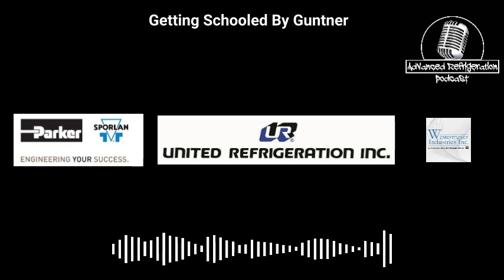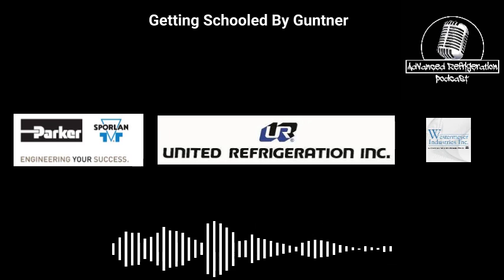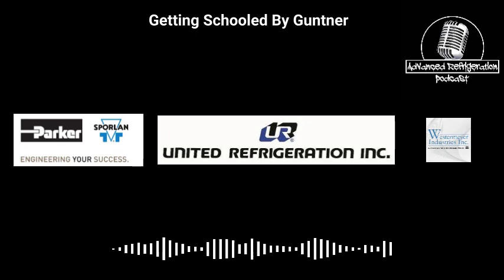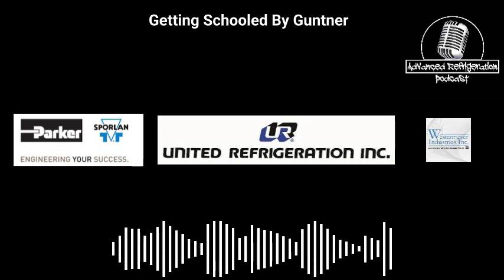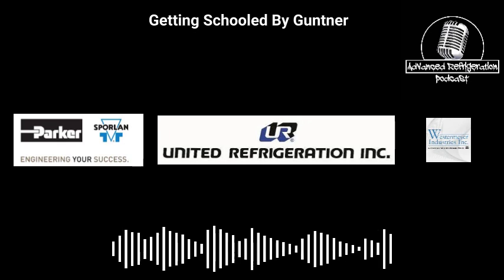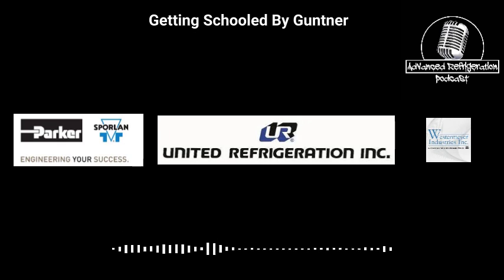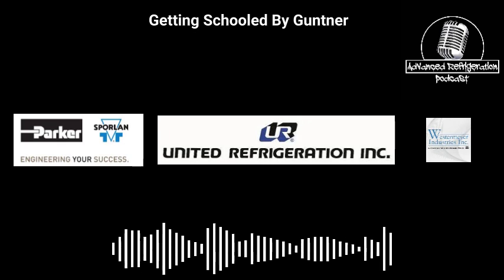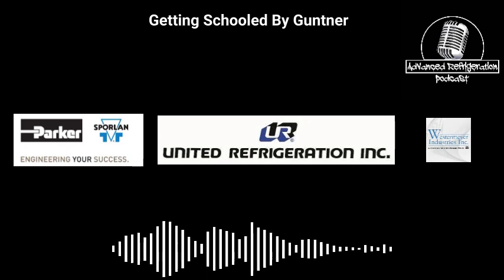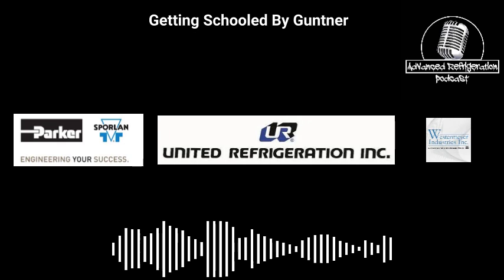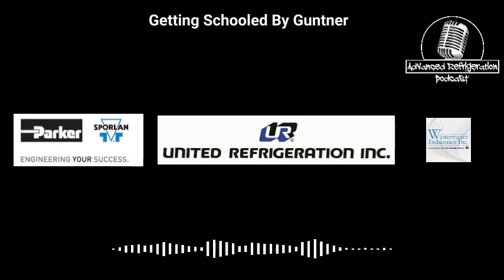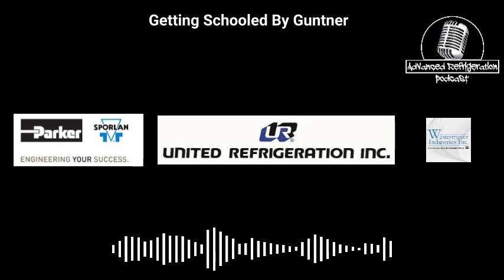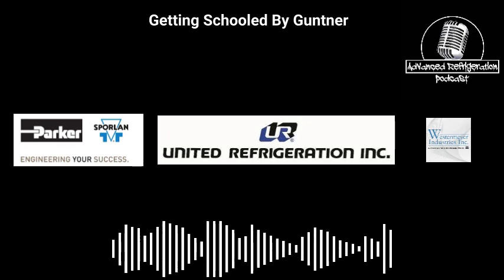There are also a lot of different settings on here. On the controller, you can do a secondary set point. This is usually used on a unit that's standalone. A lot of sites have standalone units and don't have a BMS system. A lot of grocery stores have it standalone, but they might need two set points, one for winter and one for summer. If you have it set up properly with the proper sensors, you can put two set points in the controller, and based on the ambient temperature, our controller will know when to switch, with one set point when it's over 60 degrees Fahrenheit and another when it's under 60 degrees. And that's all done by itself.